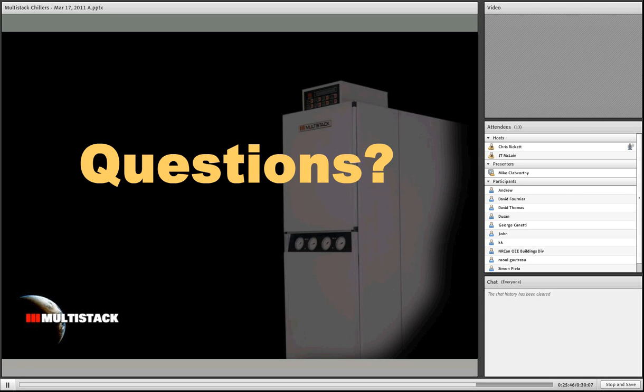And so I realize we've moved pretty quickly, and hopefully you've been able to follow it, but what I tried to show you are a couple of ways that through the use of heat recovery modules or the same modules arranged in a heat pump system, we can take advantage of the modular chiller system's ability to make hot water. One of the things that we didn't talk about was that these systems can make water as hot as 180 degrees Fahrenheit.